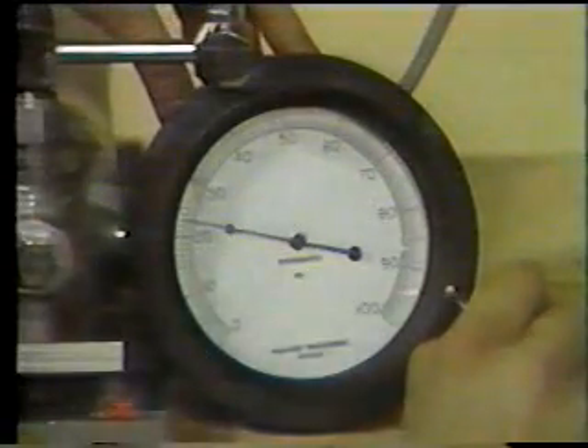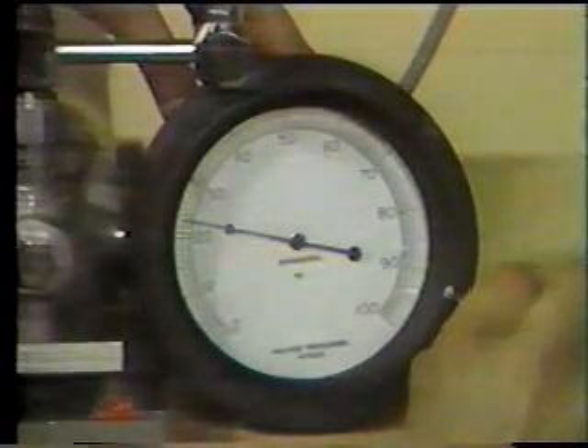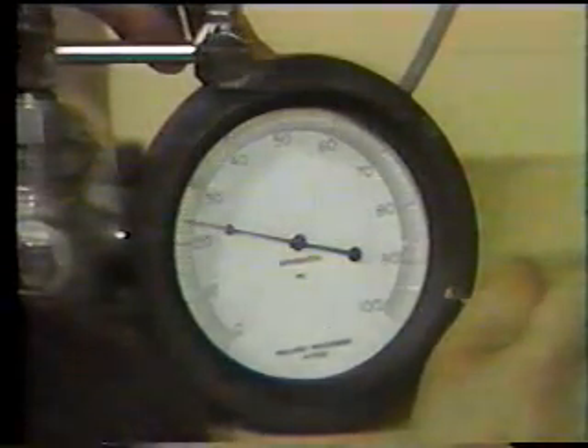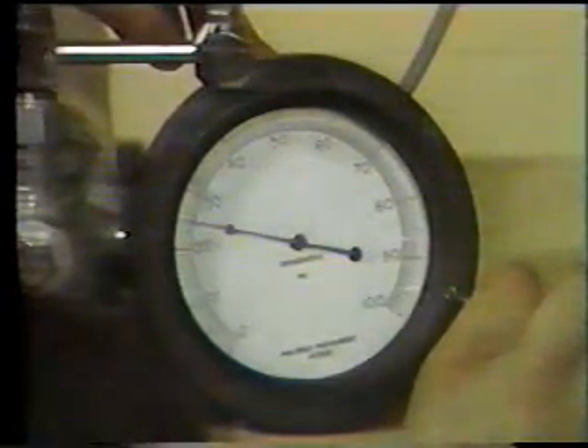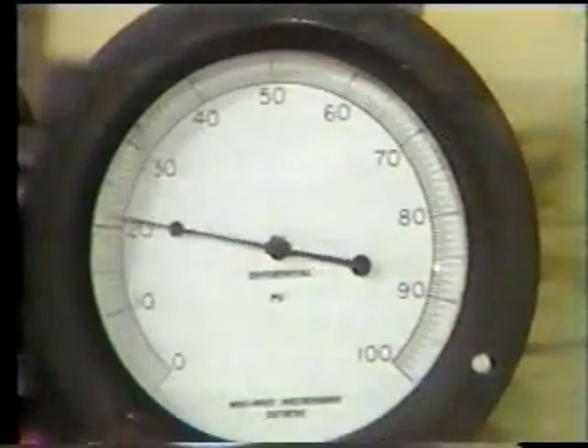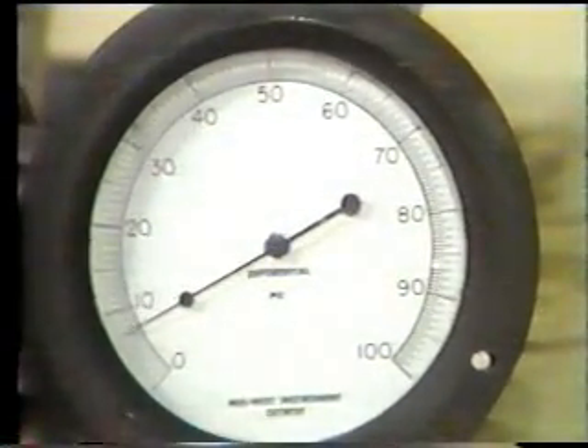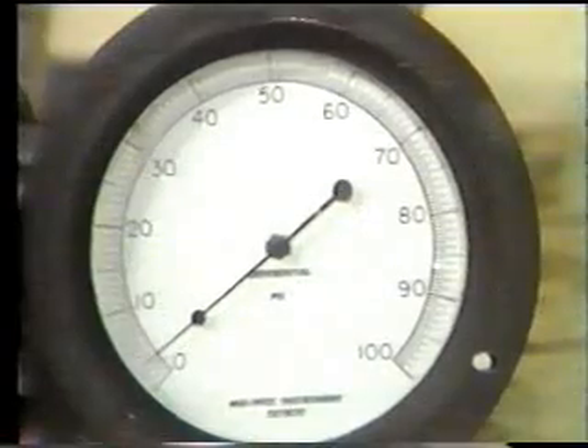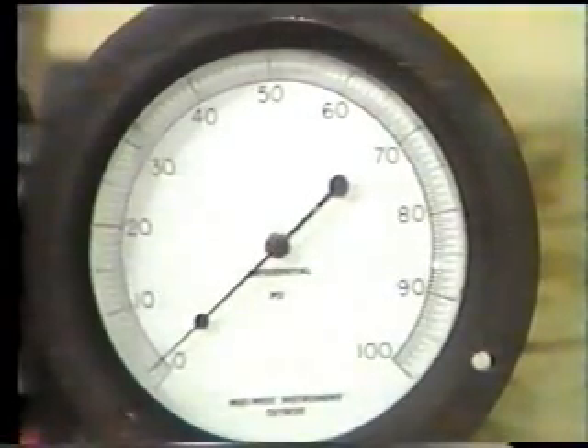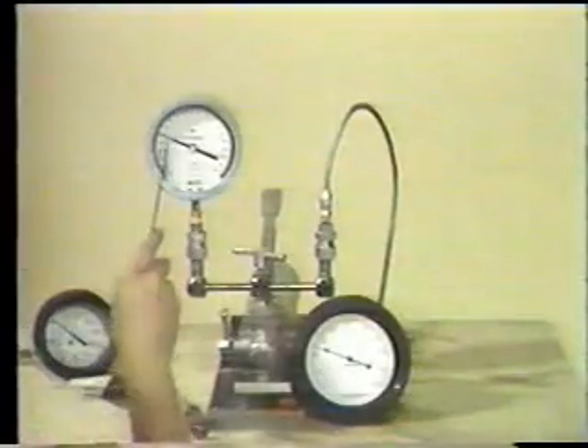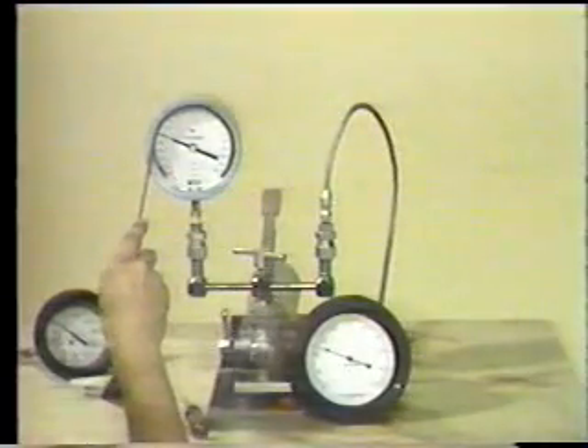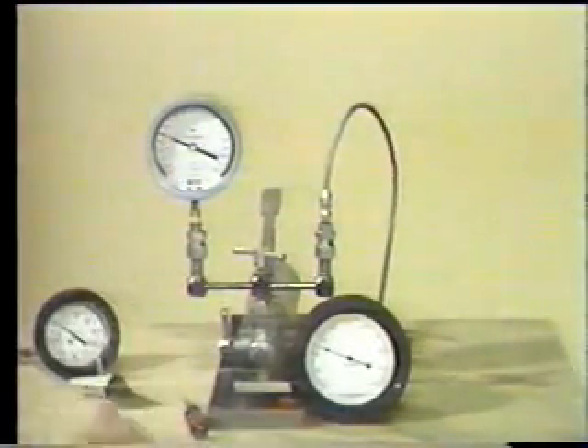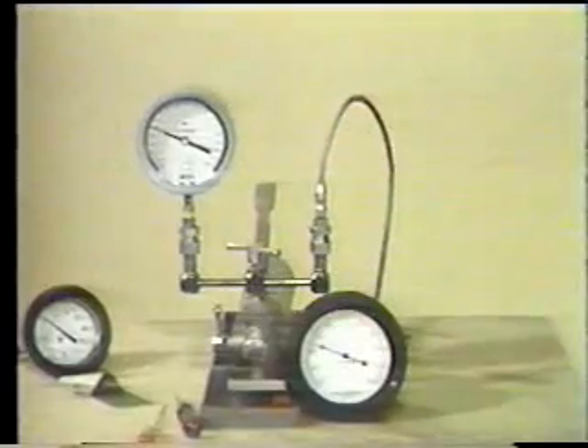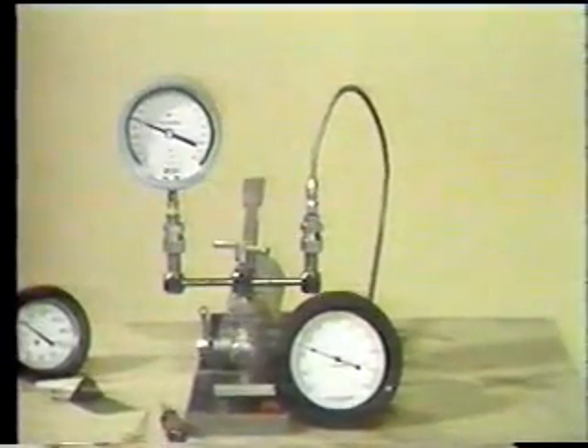Use the adjusting screw on the face of the gauge to rotate the face to the correct setting. Now decrease, then increase the pressure to check gauge repeatability. Both indicators should indicate the same. If an adjustment is made, recheck the gauge repeatability.